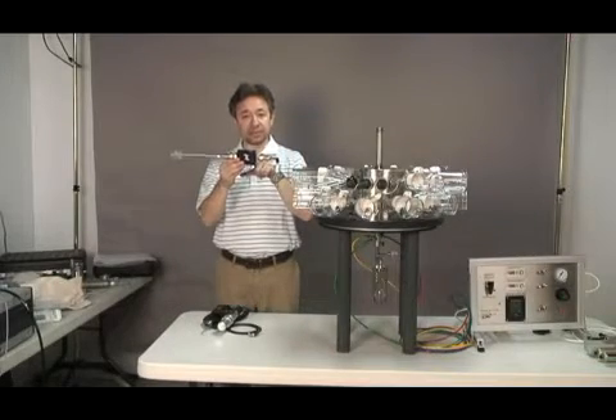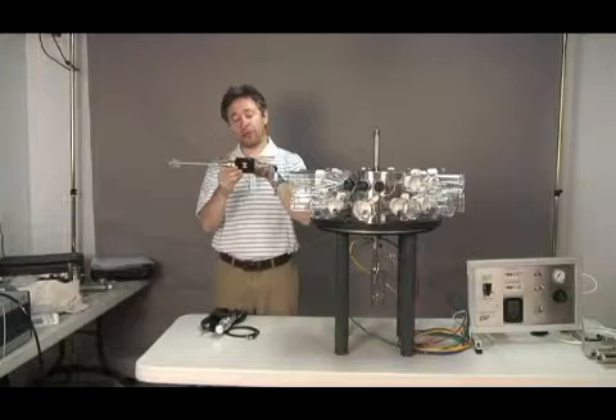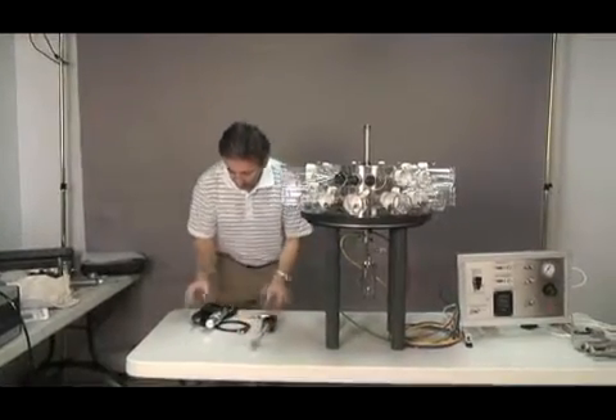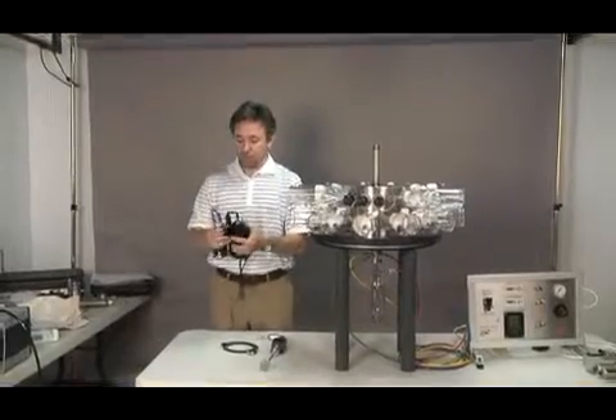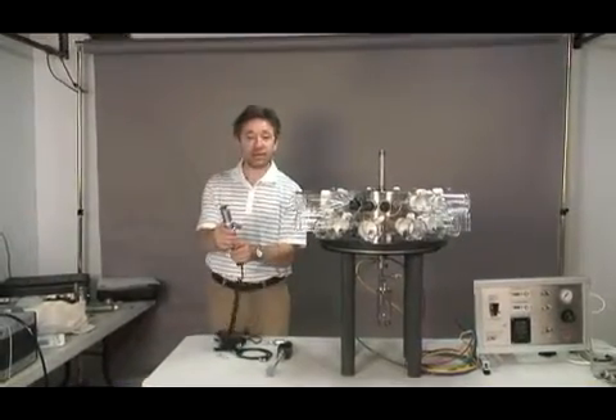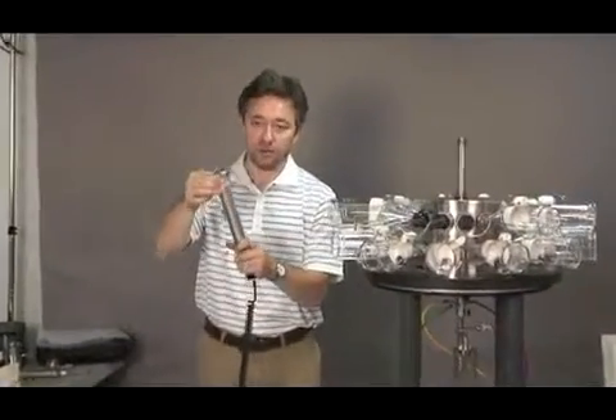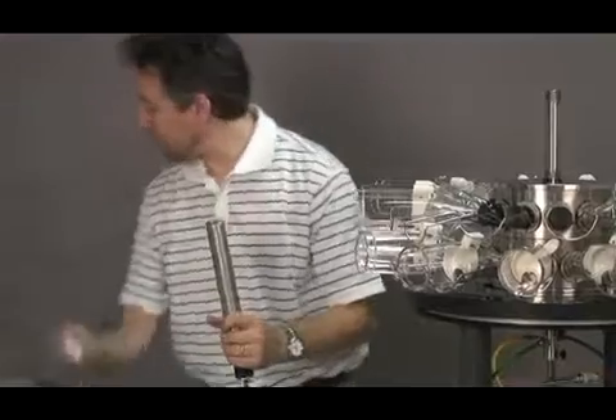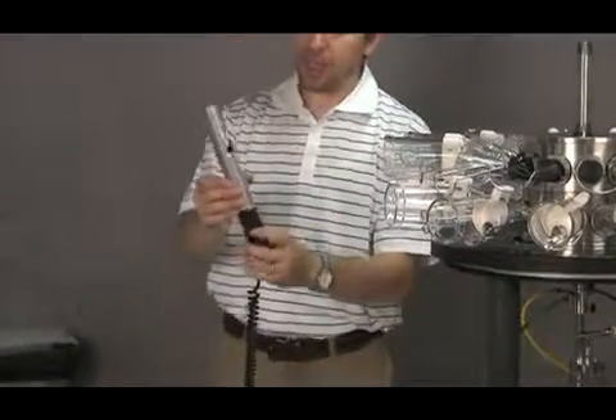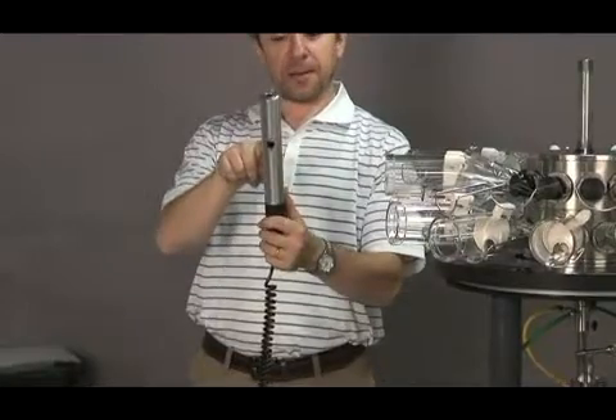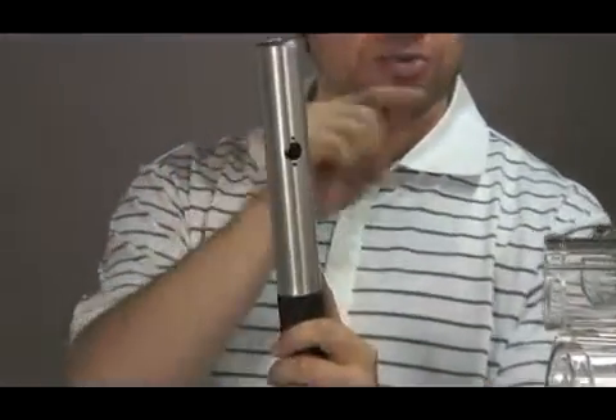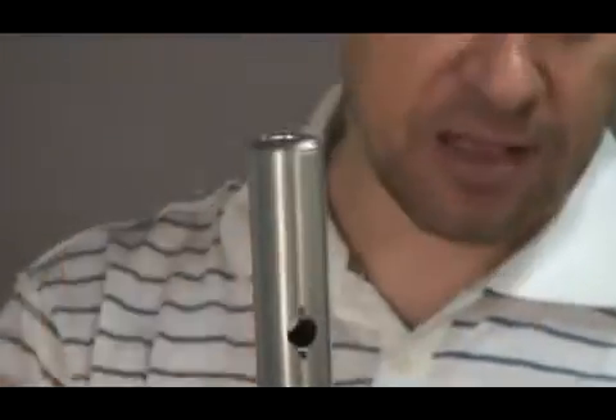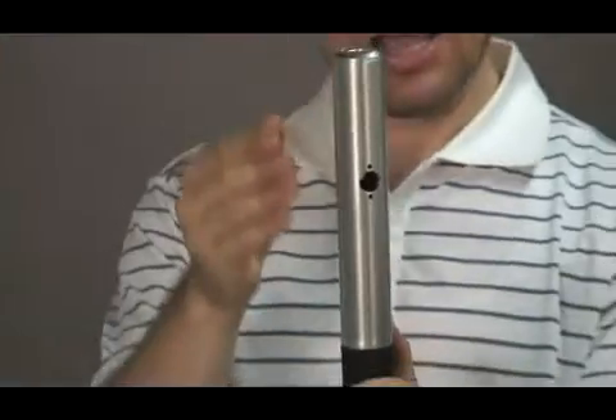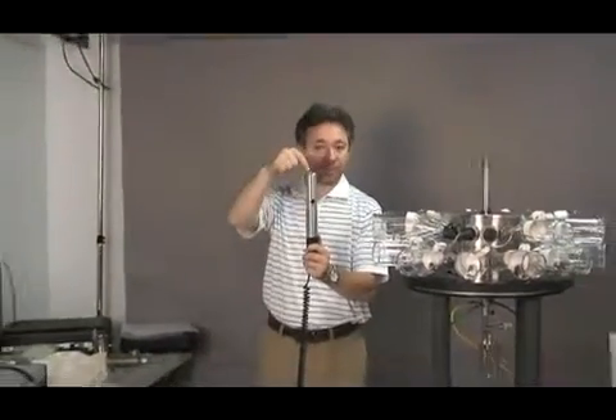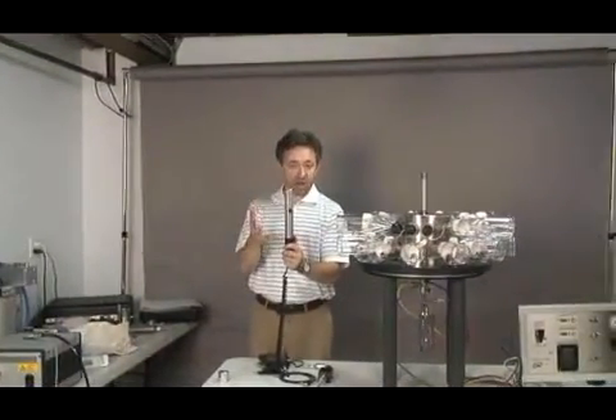In order to mount the clear lens adapter, which is going to come as a separate item with the probe, first of all, we have to remove the sleeve from the probe and put it into its case, not to lose it. Now you see, this is the hole where the aerosol stream sampling from the tower will come through, and the clear lens adapter makes sure that every single particle is going in a laminar way and is giving a light signal to the probe detector that is at the tip of the probe, so we have an accurate counting.